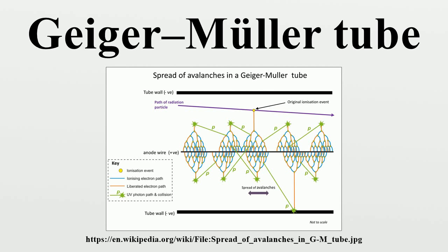Low-energy gamma and X-ray detection. The lower-energy photons interact better with the fill gas, so this design concentrates on increasing the volume of the fill gas by using a long thin-walled tube and does not use the interaction of photons in the tube wall. The transition from thin-walled to thick-walled design takes place at the 300 to 400 keV energy levels. Above these levels, thick-wall designs are used, and beneath these levels the direct gas ionization effect is predominant.